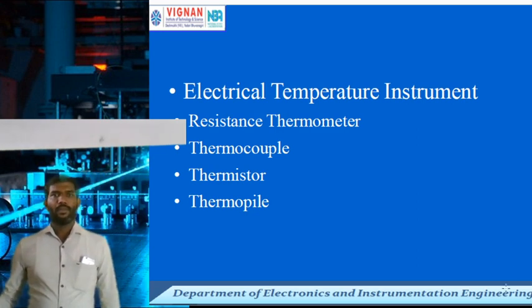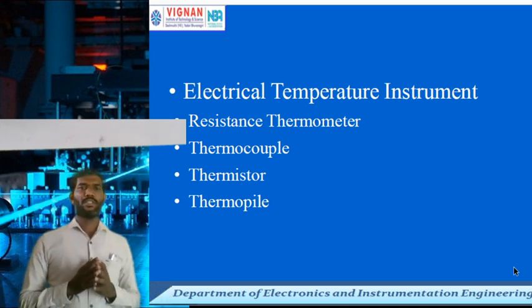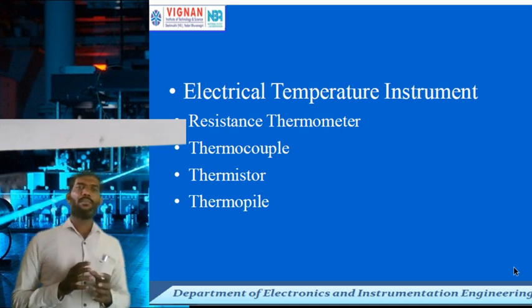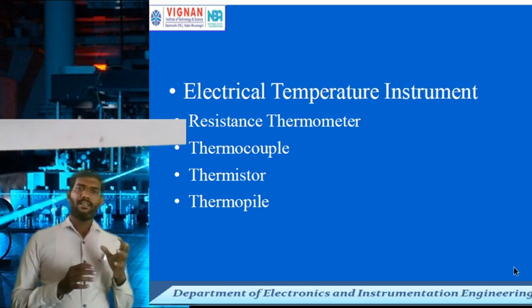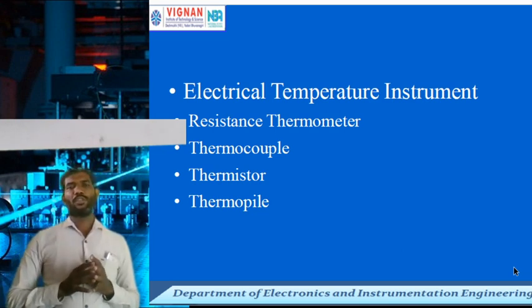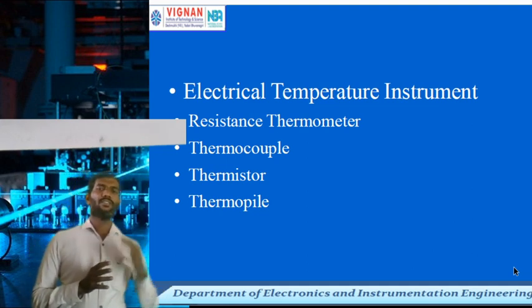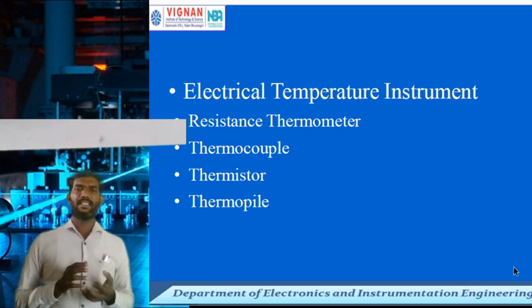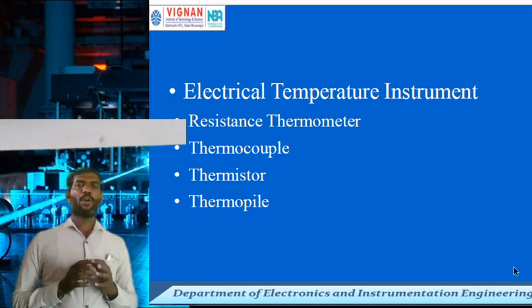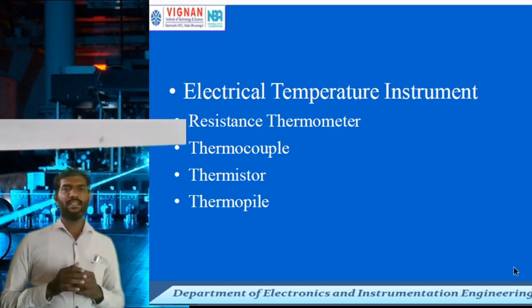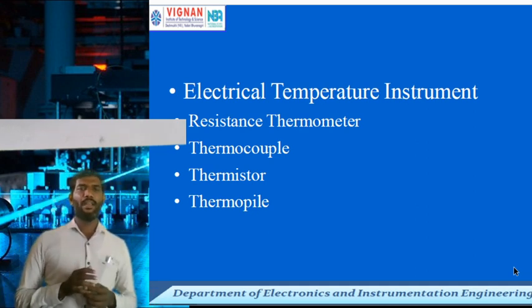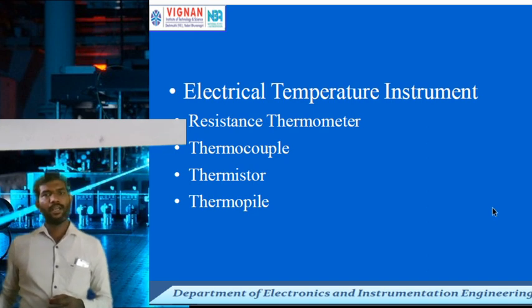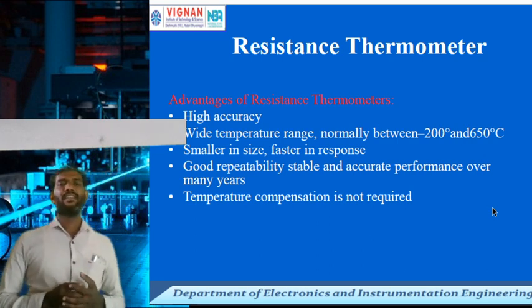Different types of electrical temperature measuring instruments are used. They are classified into different types: resistance thermometer, thermocouple type, thermistor type, and thermopile. Resistance thermometer is a positive temperature coefficient — when the temperature increases, resistance also increases. Thermistor is a negative temperature coefficient — when temperature increases, resistance decreases. Thermocouple is formed by two dissimilar metals, where a hot junction and cold junction are formed. Thermofile is when a number of thermocouples are connected together.